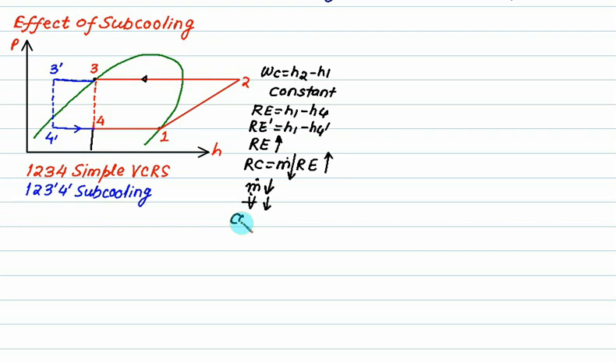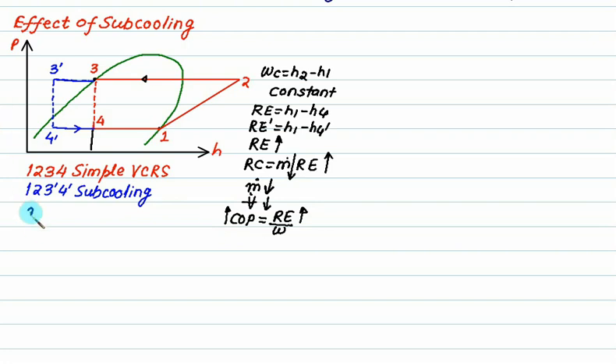The COP is defined as RE divided by W_C. Since RE is increasing and W_C remains constant, the COP also increases. To conclude for sub-cooling: mass flow rate decreases, COP increases, compressor work shows no change.